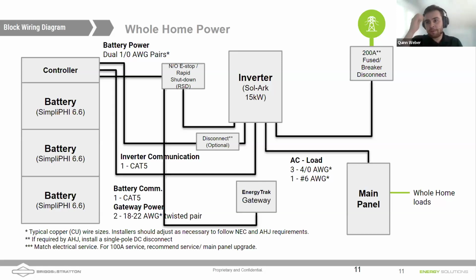So with that, normally a 15 kilowatt inverter, for instance, a 100 amp panel like we were talking about, 20 amps would be your breaker feeding the inverter. But that isn't going to work on the 15K because we want to feed all 100 amps to, for instance, a critical loads panel or a load panel downstream. We need a full 100 amp breaker there. So by using PCS, you can limit the amount that the inverter is pushing back to the grid or energizing that busing. And that's all part of our grid controls through the regular process of programming the inverter.